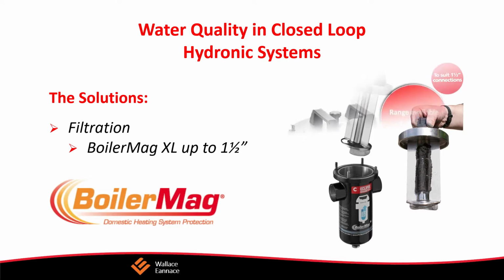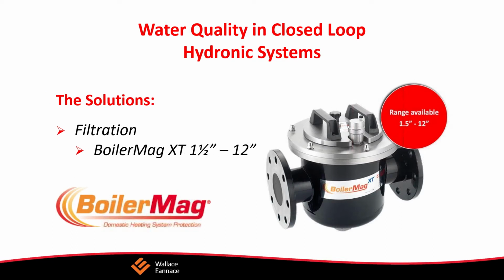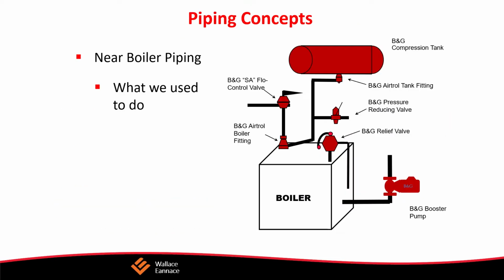And also, the problem today is that this isn't your father's boiler. You have much narrower waterways, and these waterways can be subject to clogging. You have ECM pumps. Remember, they have a permanent magnet, and they have a low tolerance for a thing called magnetite.